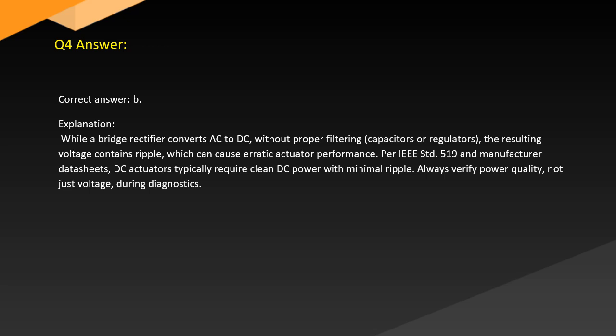Answer. Correct answer B. Explanation. While a bridge rectifier converts AC to DC, without proper filtering capacitors or regulators the resulting voltage contains ripple, which can cause erratic actuator performance. Per manufacturer datasheets, DC actuators typically require clean DC power with minimal ripple. Always verify power quality, not just voltage, during diagnostics.